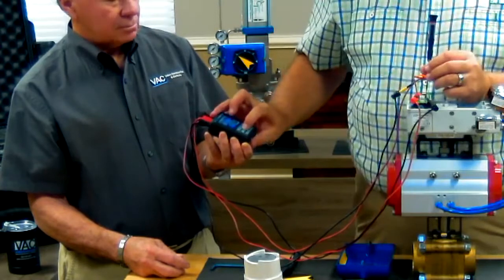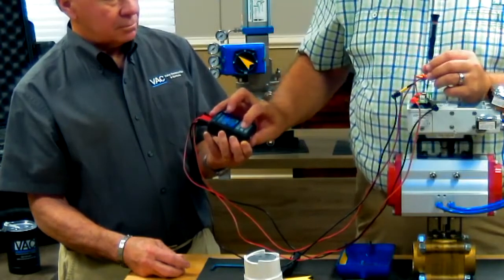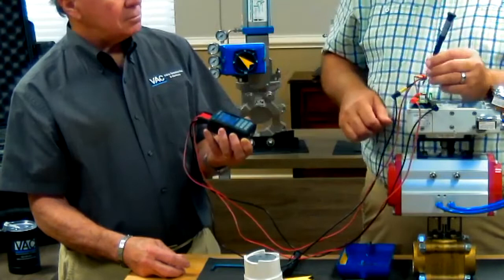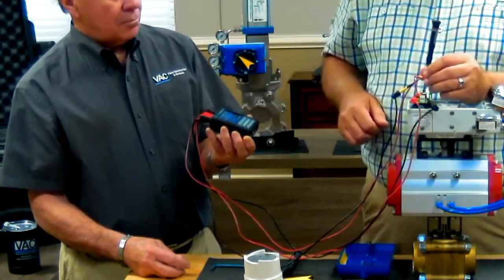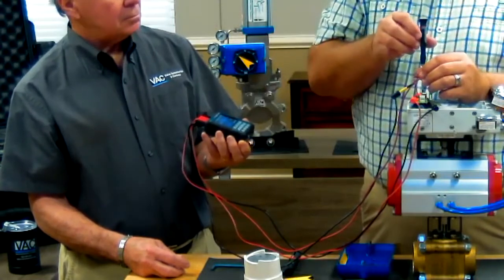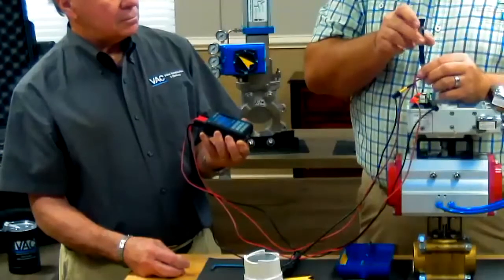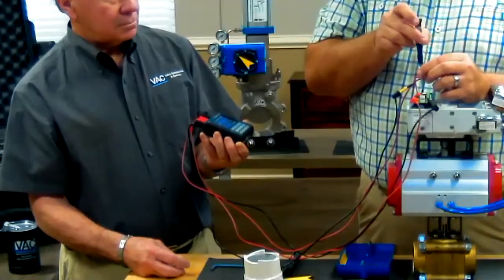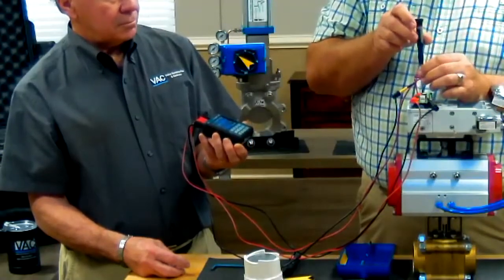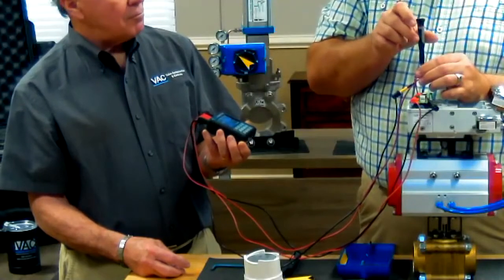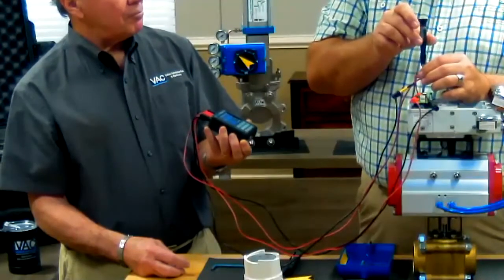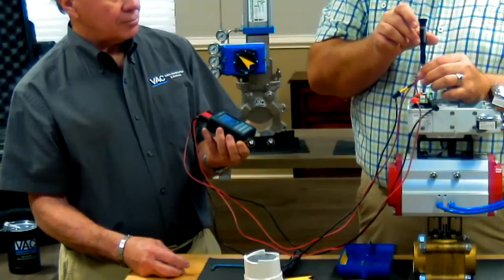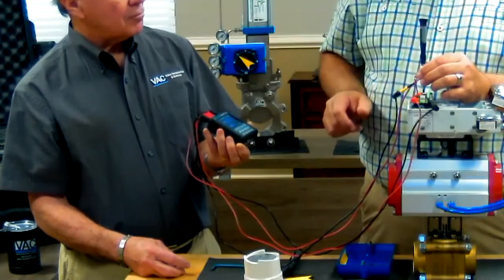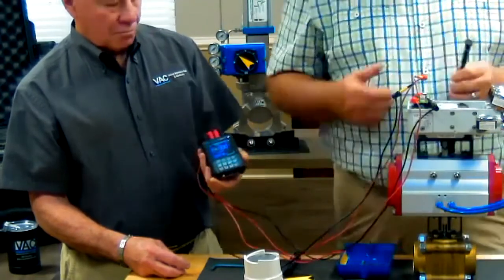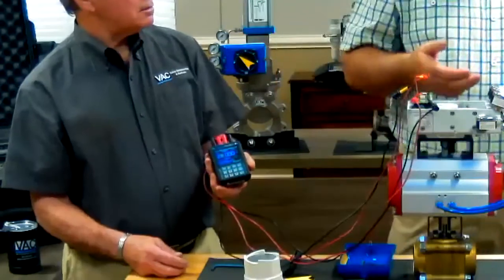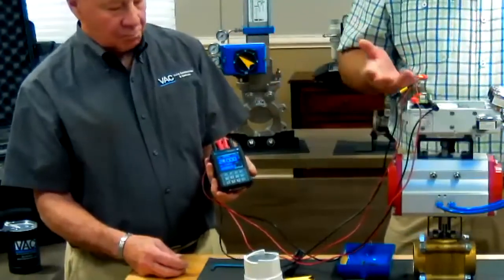And now I'm going to go up to 20, and do a count, and just bring my span with the trim potentiometer into 20 milliamps. So there's my calibration - that's calibrating feedback. I added feedback and calibrated it in just a couple of minutes.